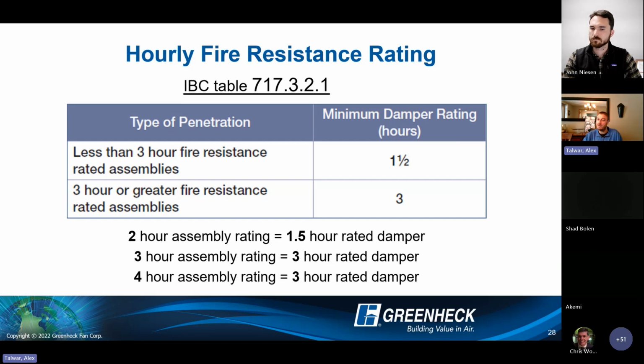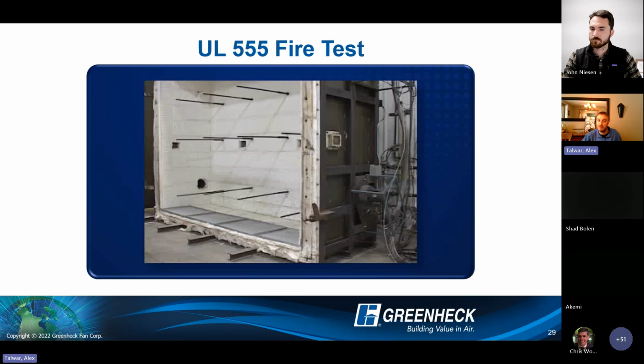3 hour rated damper. So that's a word of caution to avoid over-speccing if you don't need to, right? You don't pick a 3 hour damper if you don't need a 3 hour damper, because that could limit your options and could start becoming more expensive. So a 1.5 hour rated damper is good to use in 2 hour, 2.5 hour, 2 hour 59-minute walls, not a 3 hour wall. Once you hit that 3 hour rating, now you need the 3 hour damper, but you can also protect a 4 hour assembly as well.